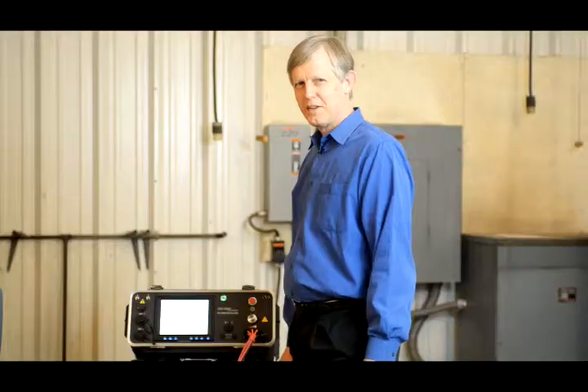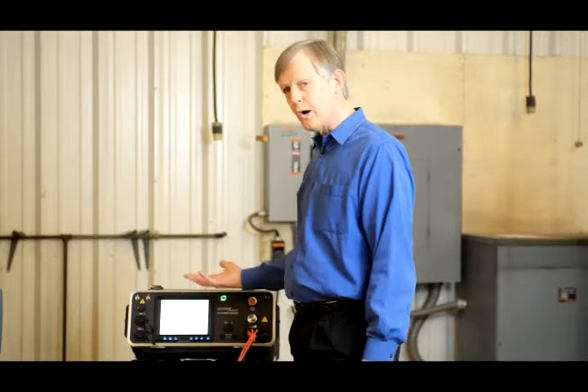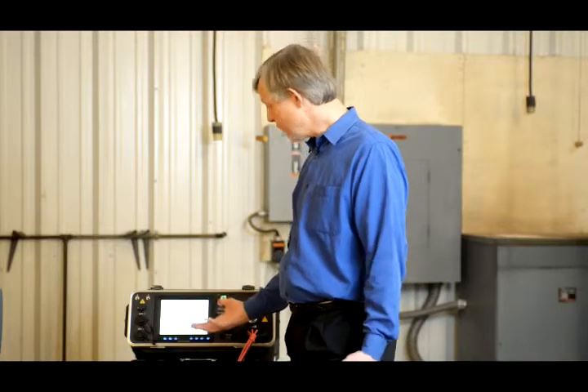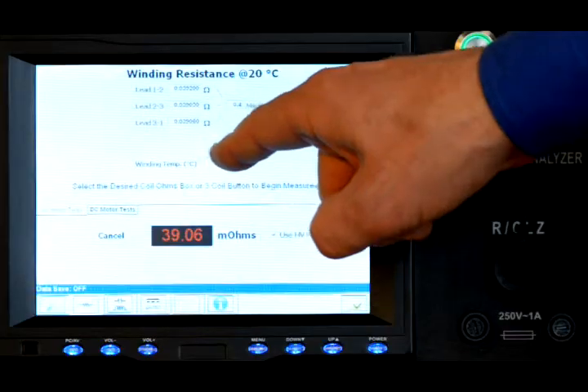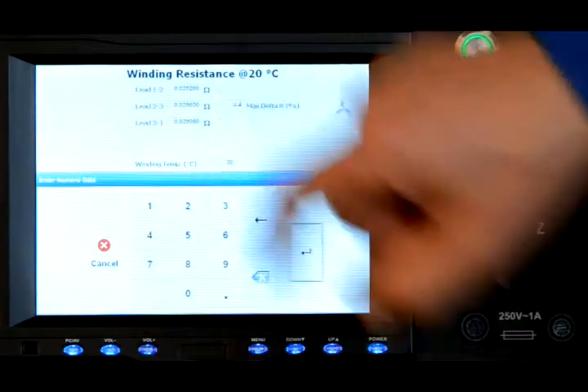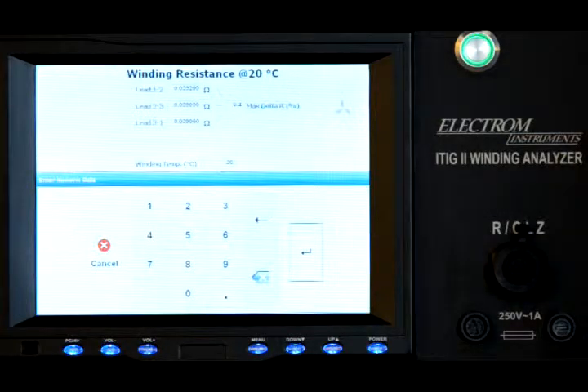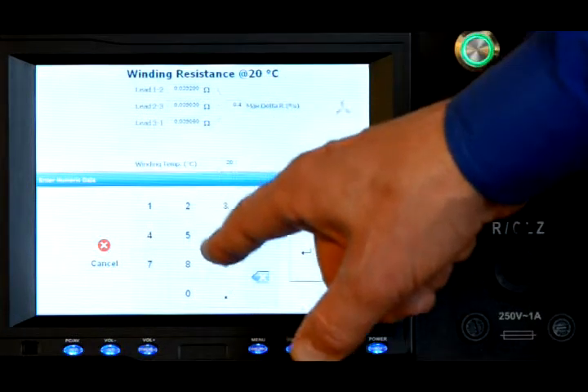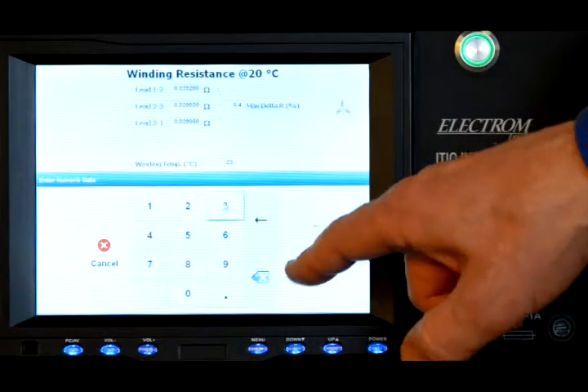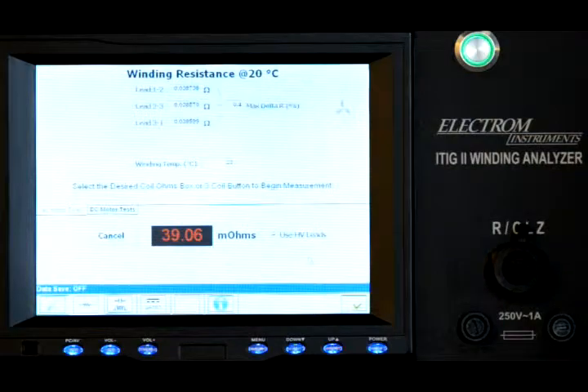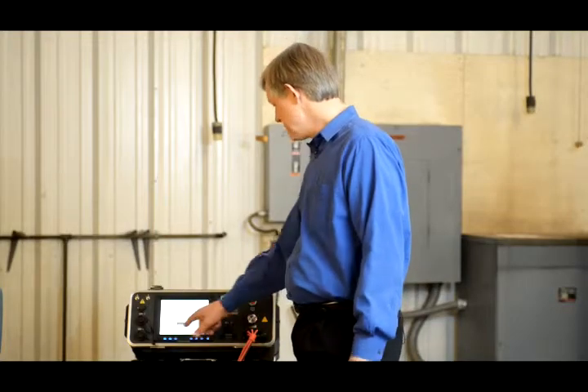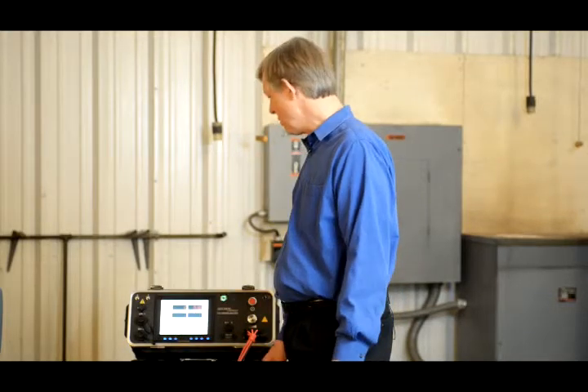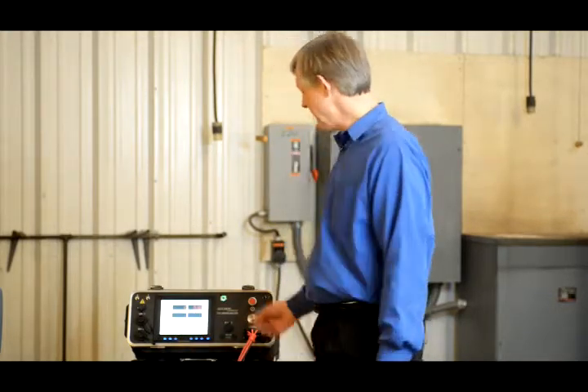This temperature can be changed before or after you do the measurement. So let's say we have 23 degrees instead of 20. Click in the field and punch in the temperature. For example, instead of 20 degrees, 23 degrees. Enter. The numbers change. They're now corrected to 23 degrees and the test is finished. So now we will move on to the next measurement, which is a megohm measurement, and do that manually.